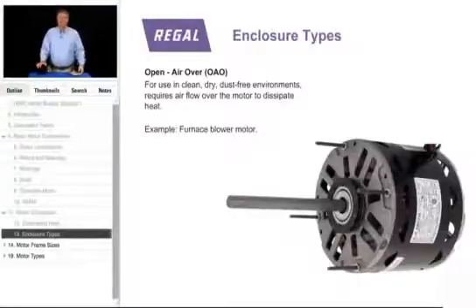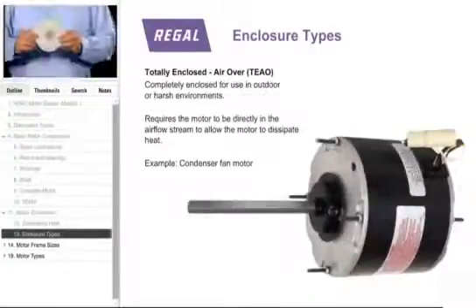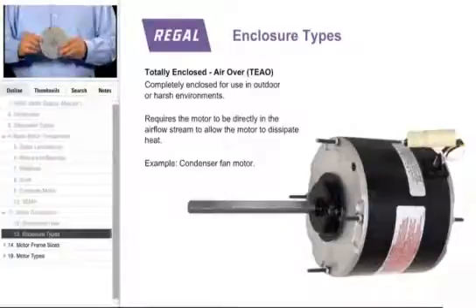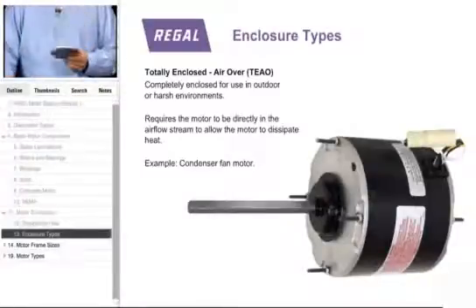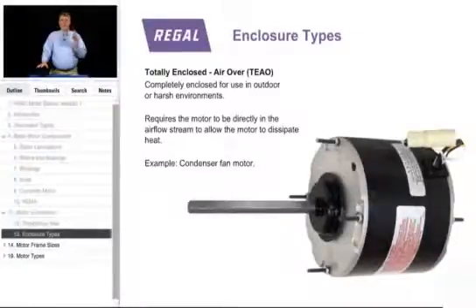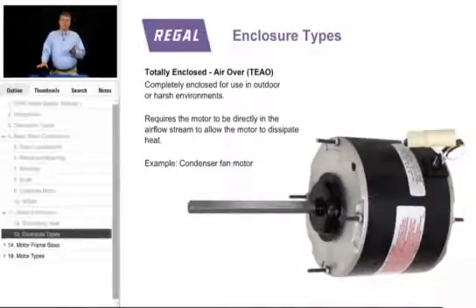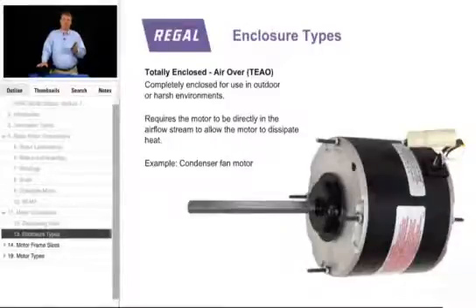The next type is totally enclosed air over, or TEAO. This motor is completely enclosed — the shell and the end brackets — and is typically in an outdoor condenser fan application. The air over is the key to this motor; it has to be located directly in the airstream to dissipate heat.